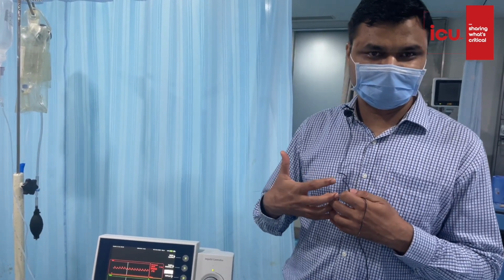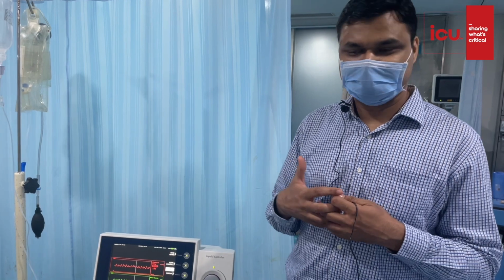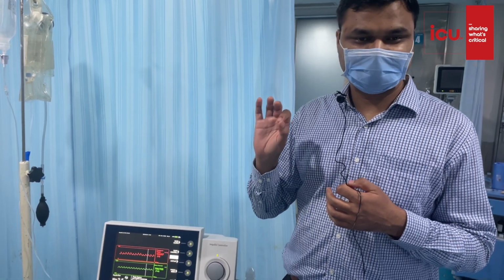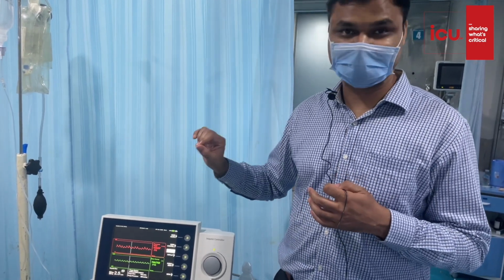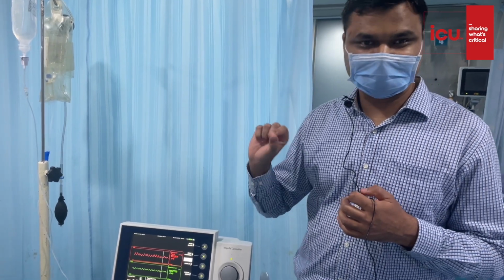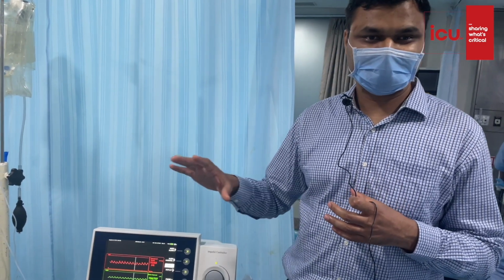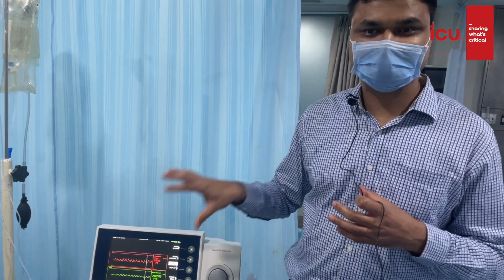Yellow alarms is something where you need to act. It may not be immediately, it's not very urgent, but you need to act on it. And red color alarm is the most critical or most dangerous, so you cannot wait to act on that. You need to act immediately when you see a red color alarm. For example, if the position of the device is changed, like both inlet and outlet are in LV or they are in aorta, that will be shown as a red color alarm on the screen, which is very critical, and you need to act on that as quickly as possible.